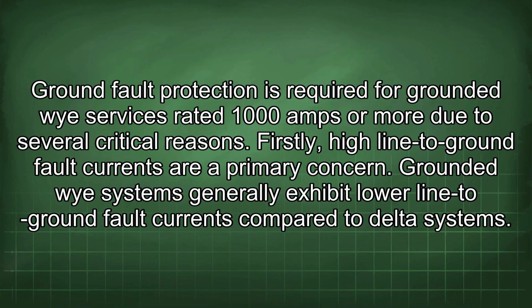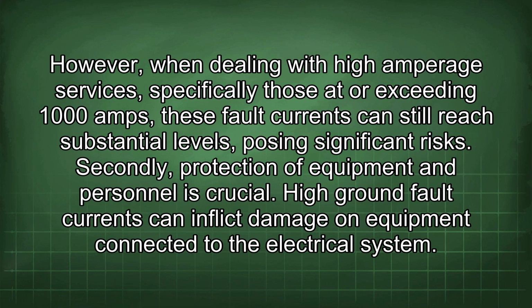Ground fault protection is required for grounded Wye services rated 1000 amps or more due to several critical reasons. Firstly, high line-to-ground fault currents are a primary concern. Grounded Wye systems generally exhibit lower line-to-ground fault currents compared to Delta systems. However, when dealing with high amperage services, specifically those exceeding 1000 amps, these fault currents can still reach substantial levels, posing significant risks.